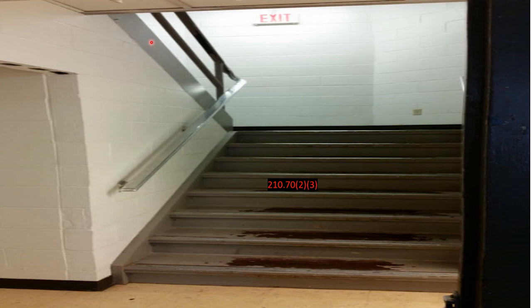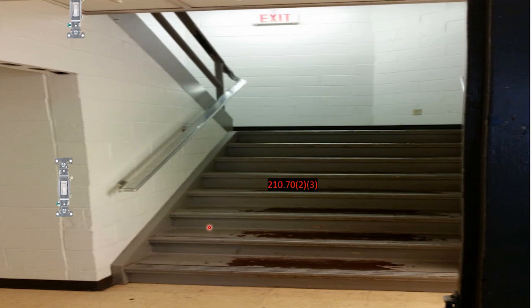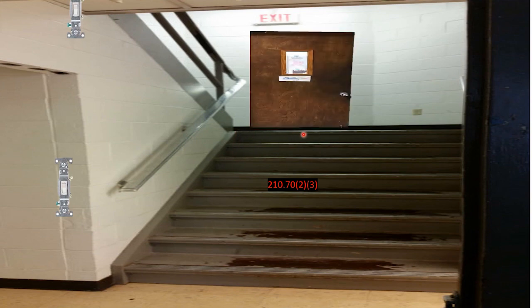With this stairwell, at a minimum you would have a switch here at the bottom and a switch up here at the top. But now let's talk about the other part of this code — if there is a landing, and it does have a doorway. So let's imagine your eighth grade teacher's door is right here at the top of this landing. According to this code, there would be required to be a switch at this location as well.